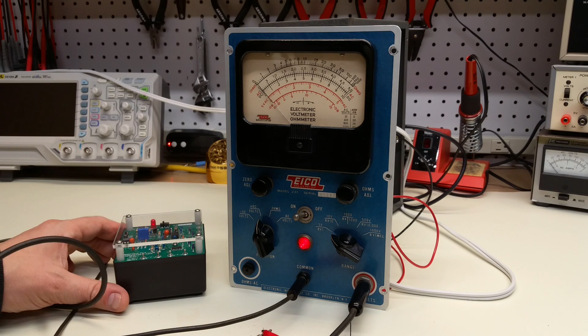I've got this not in the case. I need to be able to access four potentiometers on the inside of the chassis. But instead of two flashlight batteries, which is called for in the directions in the calibration procedure, we're going to use this DMM checker as a 5-volt DC source. And there's some standard precision resistors in that as well, so we can use it to check the ohm meter on the vacuum tube voltmeter. There's no calibration per se for the ohm scale.